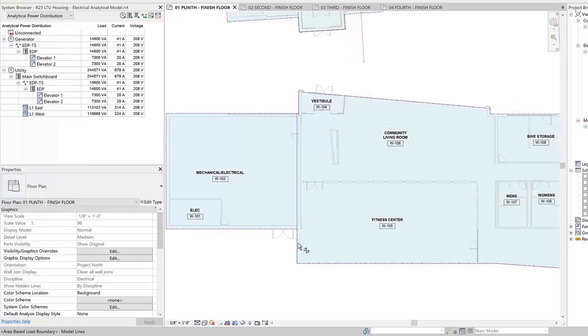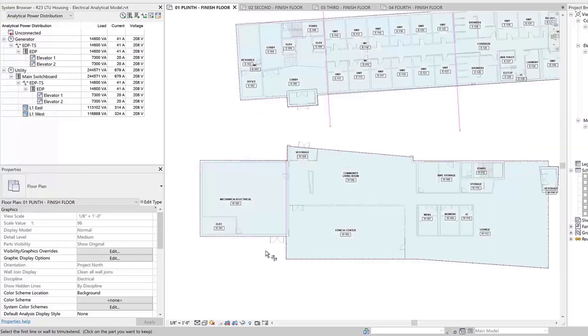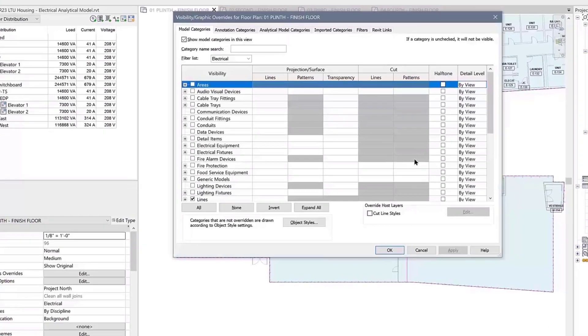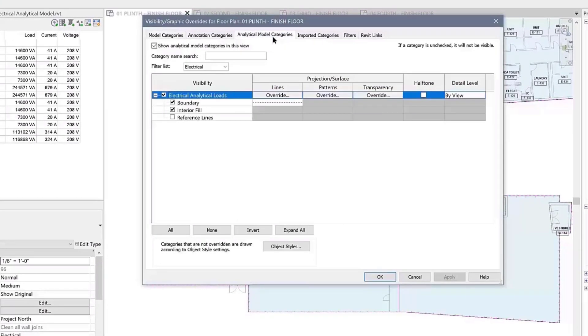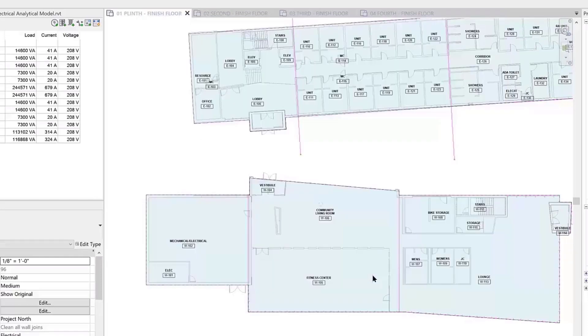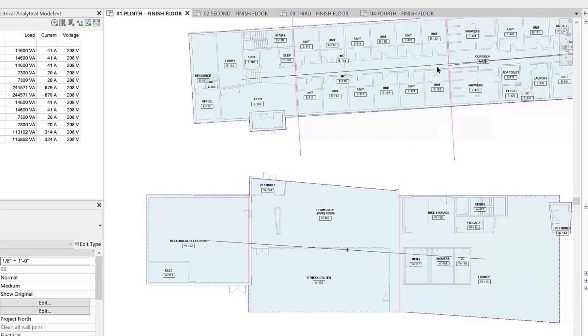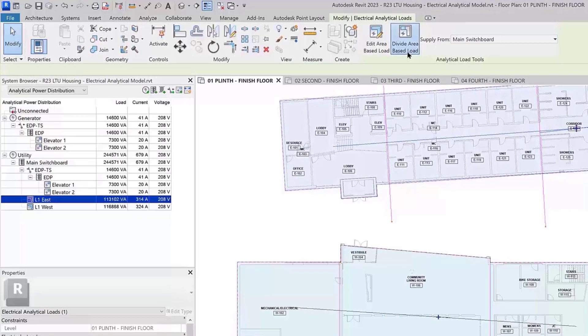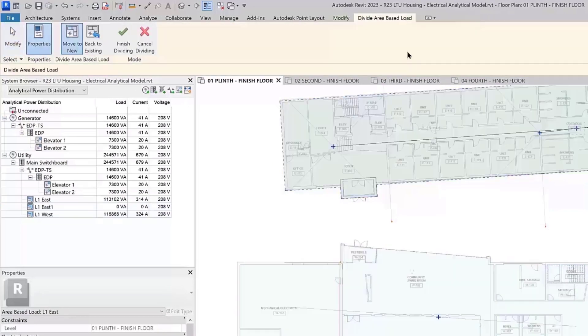To address these scenarios, you may add additional boundary lines and divide area-based loads into smaller sections. You may want to adjust the visibility graphics analytical model setting to view the reference lines. Reference lines will display area-based loads, making selection easier when you use the Divide Area Based Load command. You can simply extend or draw an area-based load boundary wherever you need to divide your area-based loads.